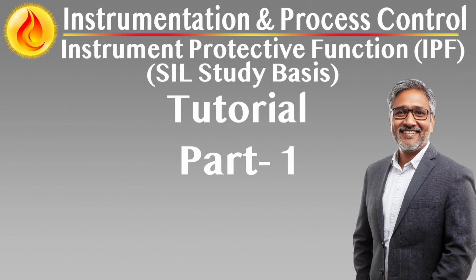Impact on SIL calculations. The fraction of total failures that are not classified as DU determines the safe failure fraction, SFF. Higher SFF means the system can meet a given SIL with simpler hardware architecture. A low SFF requires greater redundancy or fault tolerance, e.g., 1oo2 voting instead of 1oo1. The goal is to minimize DU failure rates through use of diagnostics to reclassify DU as DD, frequent and effective proof testing, and selection of field-proven or certified devices with documented failure rate data.